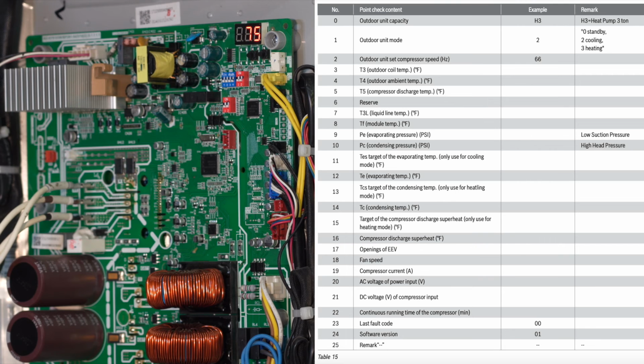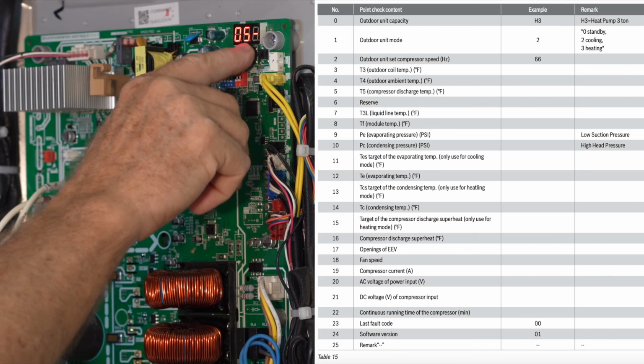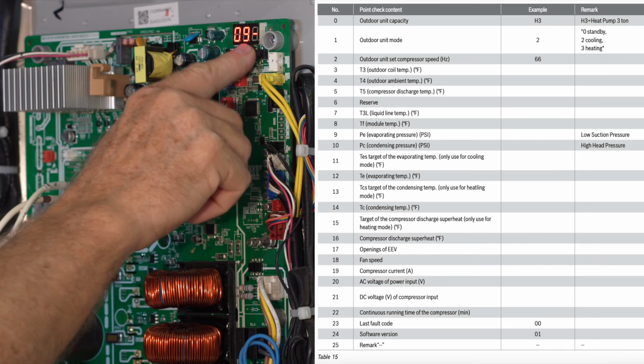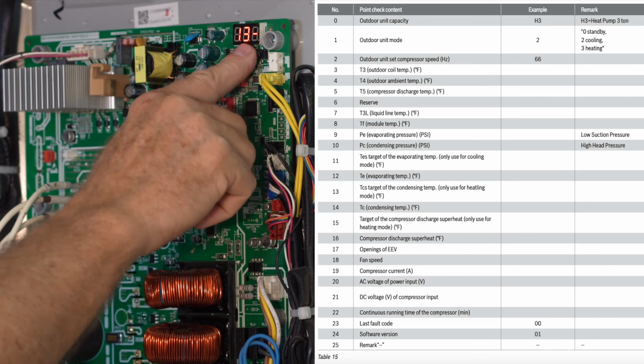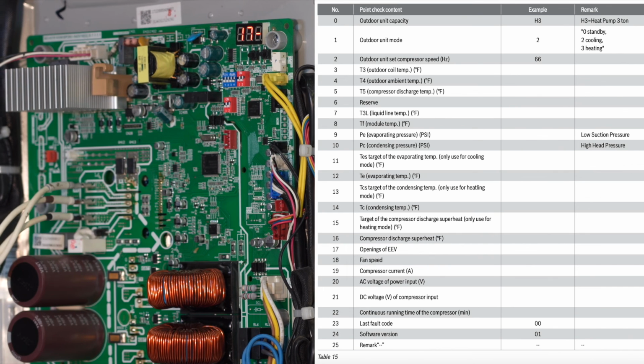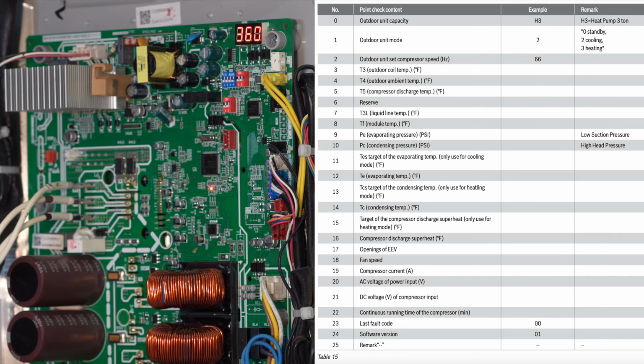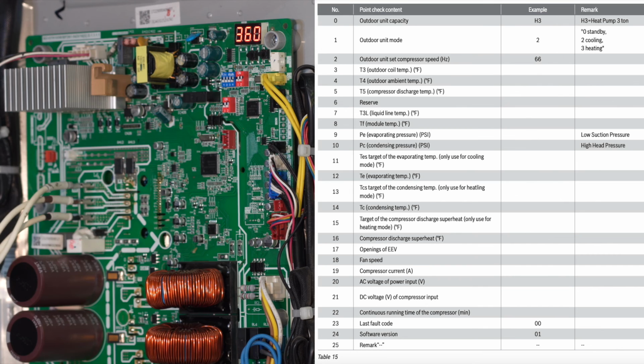Let's go down to number 17 and look at that number, because the number that you had on 17 a while ago was 480, is that correct? Correct. When the system was running in forced cooling and we were bypassing through the EEV, we were wide open at 480. So when my unit is stagnant, powered up, not running, that number's 360. So that's just sitting there in a mid position, waiting for the next call. Absolutely. What are we going to do next? Are we going to open all the way up for the cooling mode, or are we going to start throttling back and metering for the heating mode? Exactly.